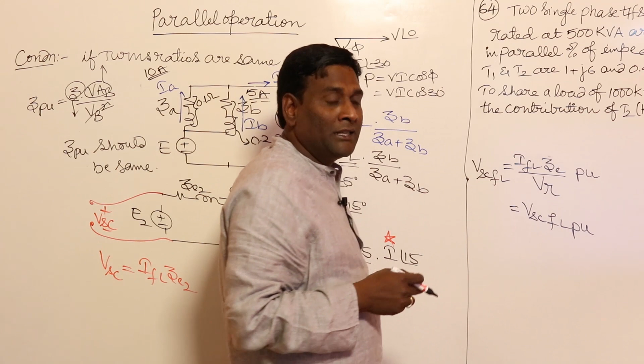So for example, the short circuit voltage is IFL ZE of the first transformer and the second transformer should be the same, because whenever one is fully loaded, the other also should be fully loaded. Under that condition, the short circuit voltage of this and of this should be the same, or ZE per unit with respect to its own kVA rating should be the same. So the point is very simple here.